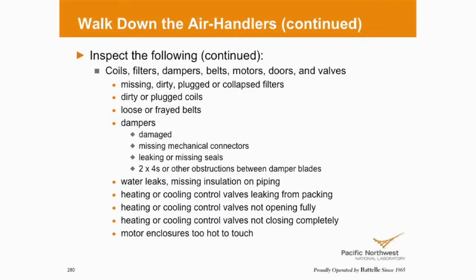Again, whether it's an air handling unit or rooftop unit, look at your coils, your filters, dampers, damper linkages, end seals on dampers if you've got them, belts, motors, doors, valves, all those things. Basically what we're looking for is condition of maintenance. Do we see coils or filters that are plugged, collapsed filters, belts that are fraying, belt debris laying on the floor, dampers that are damaged? Again, we've talked about dampers. Water leaks. If I've got a condensate drain pan on a cooling coil, is it working properly? Is the water actually coming out through the P-trap going to the drain? Or is it plugged? Or even worse, is it sucking air back in?